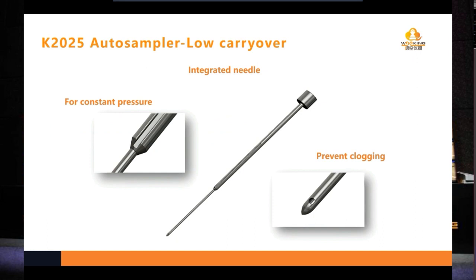And this is the needle design. The needle has a curve in the sidewall. This is for the balancing of pressure when the cover of the sample vial is injected or punctured. The injection hole is also set in the sidewall to prevent clogging from the vial.